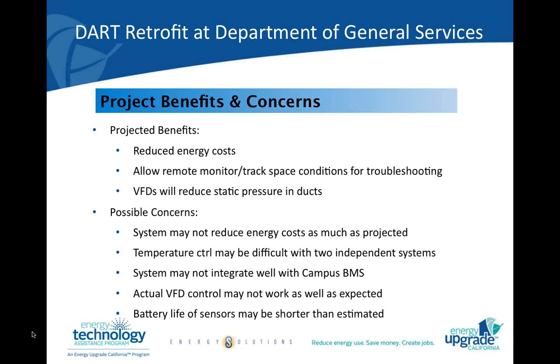The next item is whether it will integrate well with our campus BMS. We currently use Siemens Insight on this campus, and the DART system is supposed to be BACnet compatible. What we've been discovering is it has limited BACnet capability. I know it's dynamic and changing, so we'll be interested to see how it all plays out at the end, how well it integrates with what we already have. That's similar to how well the VFD control will work. And then, of course, what is the battery life on these sensors?